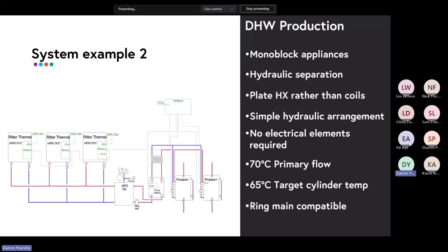And with the cascade controller that we use, that is actually managed across the array. So if you've got one heat pump which is currently going through a defrost, it'll hold the other two heat pumps in production to keep the system running. And then once that first heat pump has finished its defrost cycle, if one of the other two require it, then that one will start. So the system will only allow defrost on one of the appliances at a time. So all that sort of logic's built in on the cascade controller.